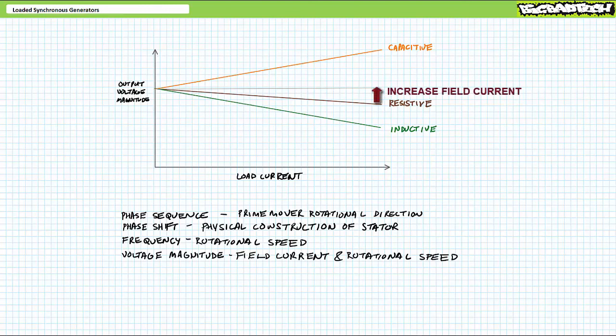For example, consider a high current demand resistive load where an operator is aggressively compensating for this anticipated reduction in voltage output by increasing field current. Suddenly, the user disconnects that load. At this present level of excitation, one might expect voltage to momentarily surge above the desired fixed value unless the operator decreases the field current in response to this fluctuation in demand.